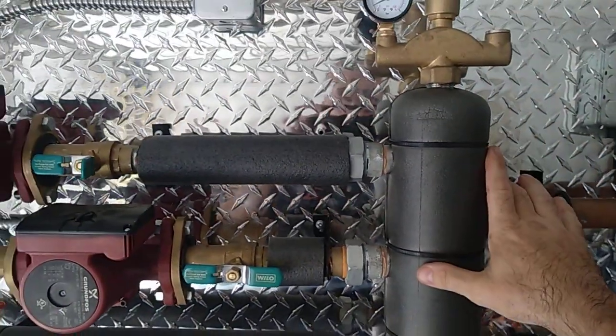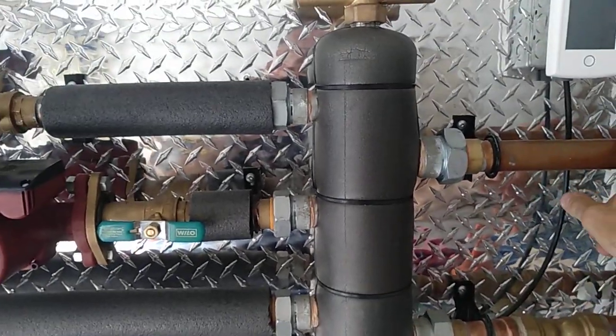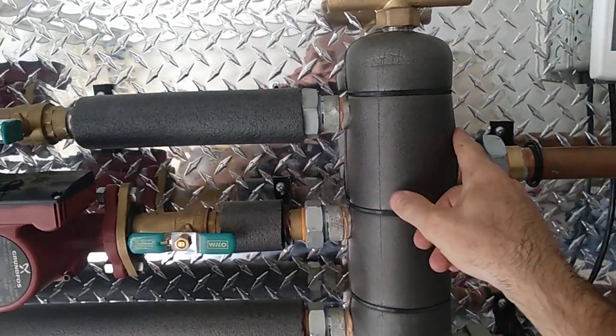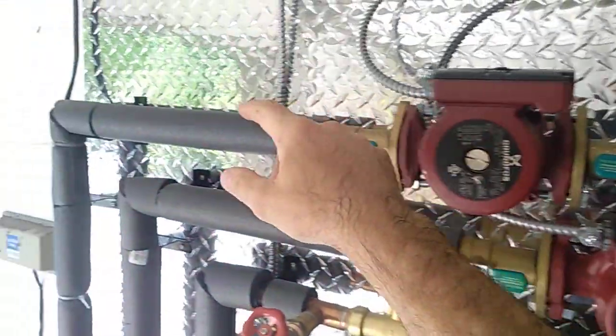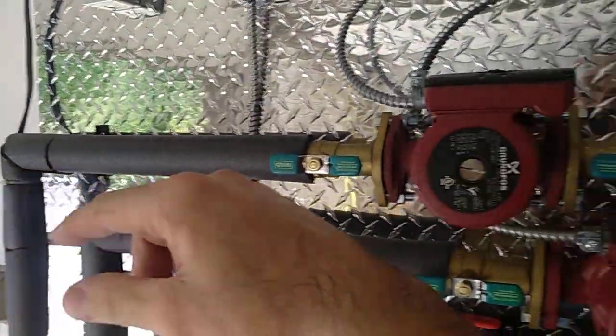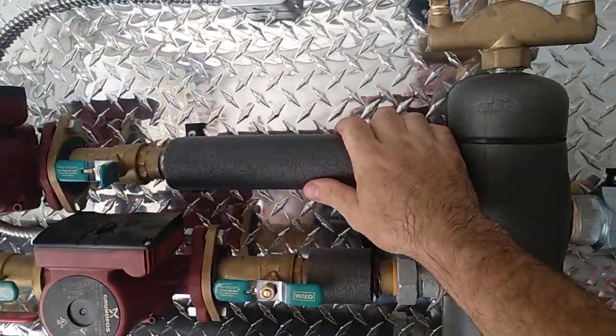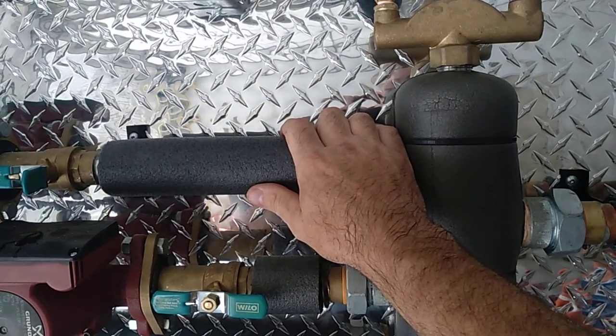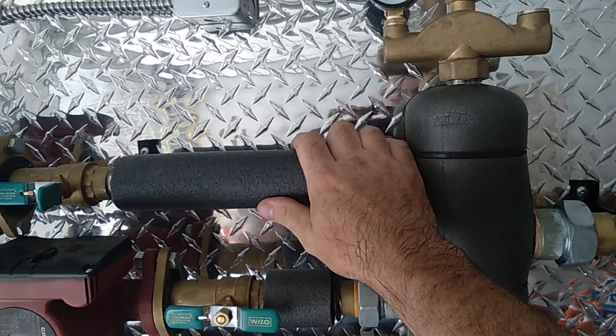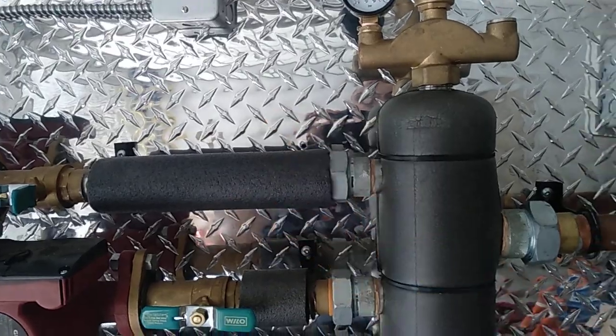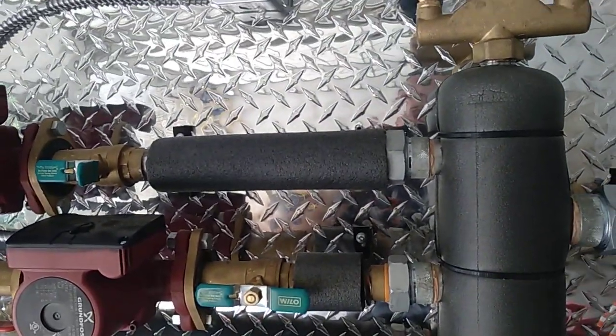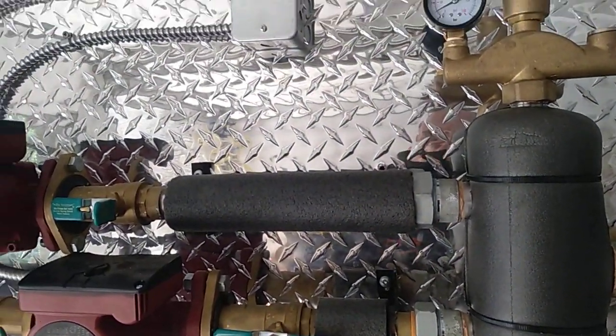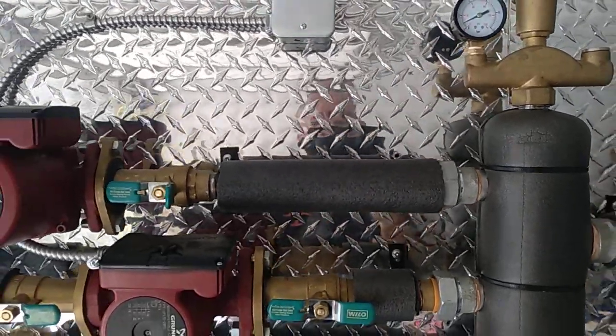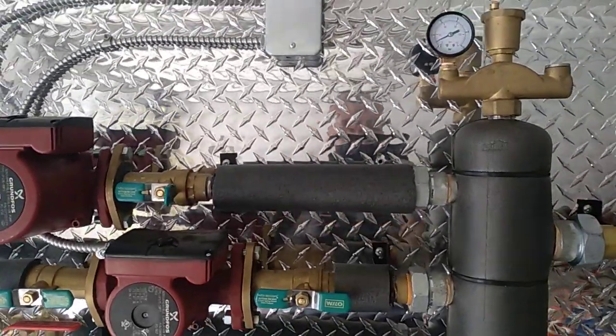What I mean about that is imagine that the hot water, it's 160 Fahrenheit, would just go straight out to the pipes and into the concrete. Now there would be, let's say, minus 10 degree concrete out there. You can easily see that 170 Fahrenheit temperature difference suddenly will cause some damage out in the slab.